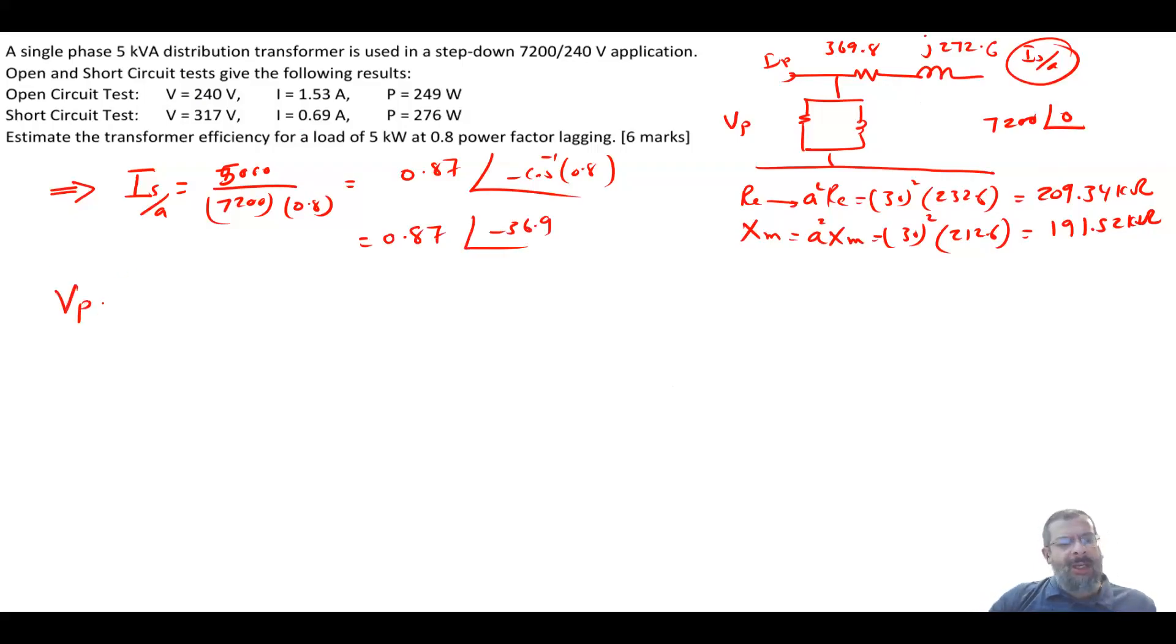Your Vp now, just a KVL, is equal to 7200 angle of 0 plus the current 0.87 angle of minus 36.9 times 369.8 plus J272.6, and this will give me a voltage of 7553.2 angle of minus 0.0254 volt, which is almost 0. These values, because I have to assume a value for the core loss.